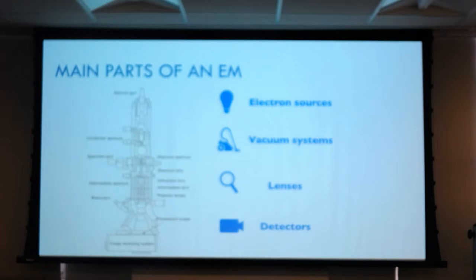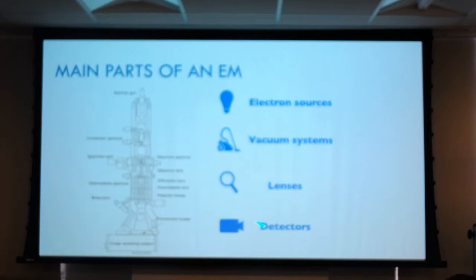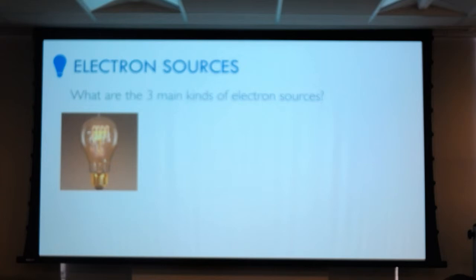Just like in a light microscope you have a light bulb, for an electron microscope you have an electron source. Because we're dealing with electrons we have to worry about electrons going through whatever medium — electrons cannot penetrate air very far — so we need a vacuum system. Just as light has glass lenses, EM actually uses magnets to bend electrons. And finally, like any good light microscope you need a detector — our detectors are actually movie cameras in a sense. So let's go into the different types. Does anyone know the three kinds of electron sources?